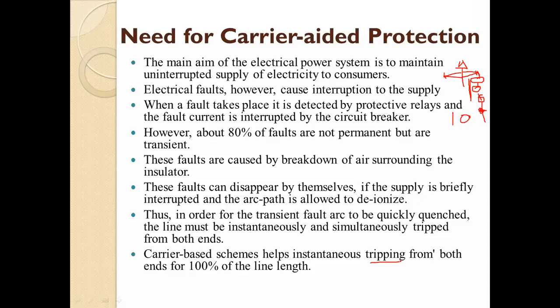And what happens in that? Whatever be the relay nearest to the fault will operate first, and the relay which is some distance away from that fault will operate after some time. Okay, means it is not operating instantaneously, means it is going in zone 2. Okay, your second relay is going in zone 2 operation. Okay, that is after some time. So this can be reduced by using this carrier aided protection.